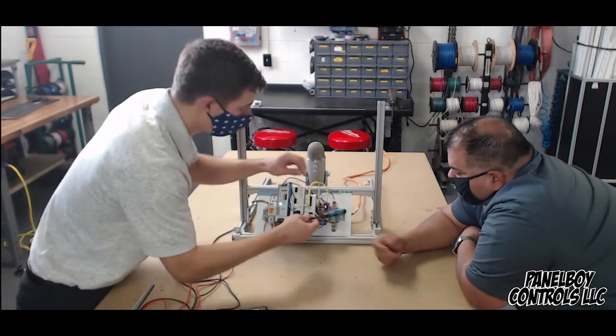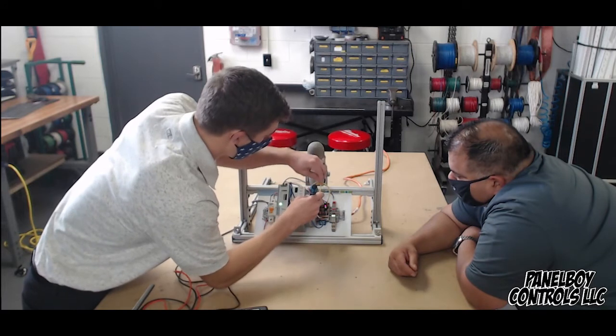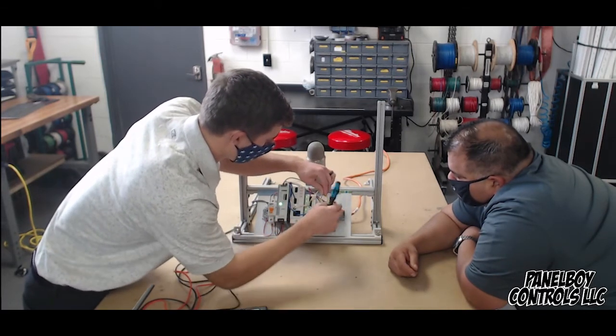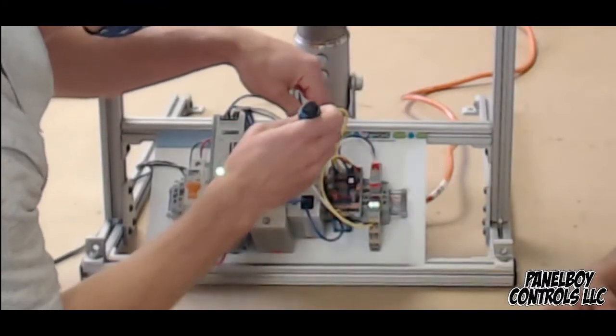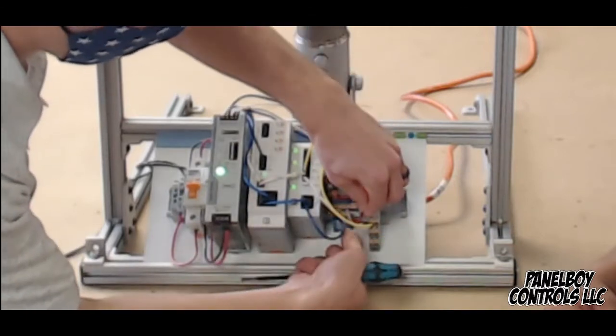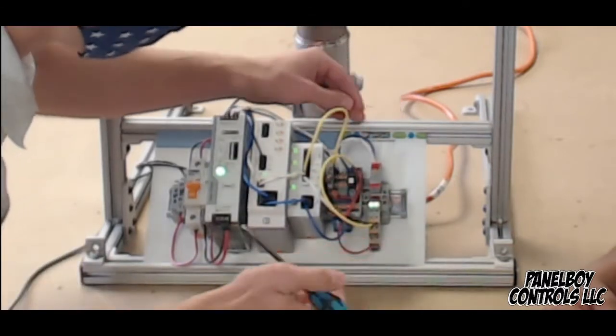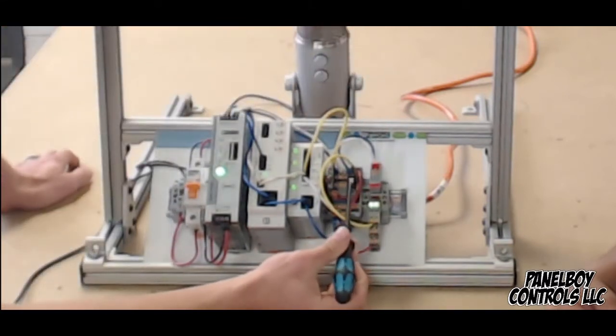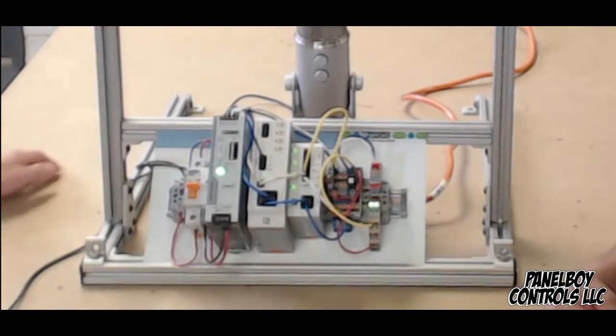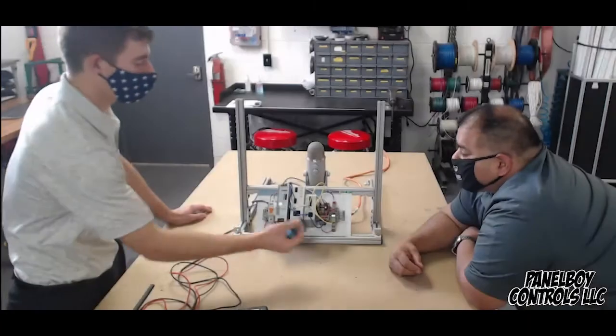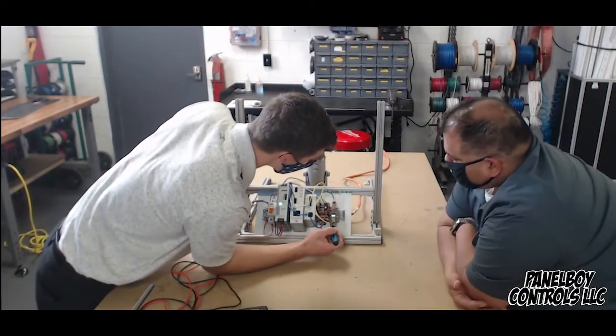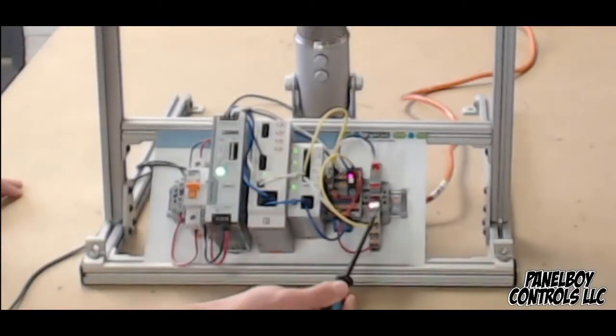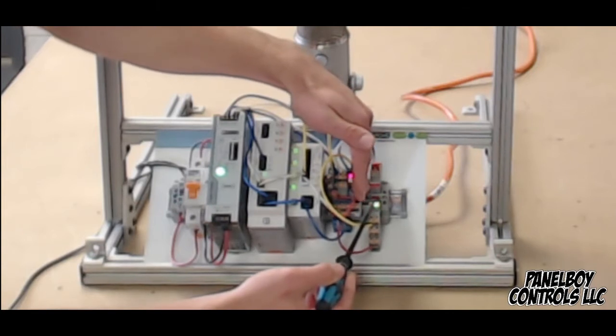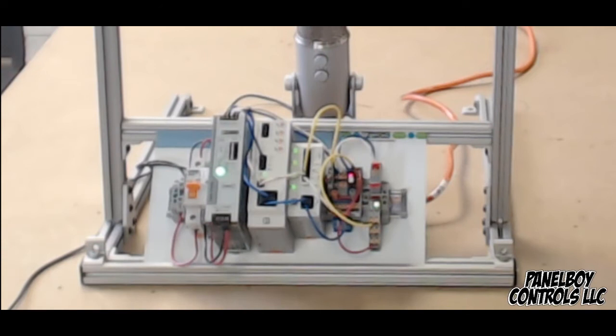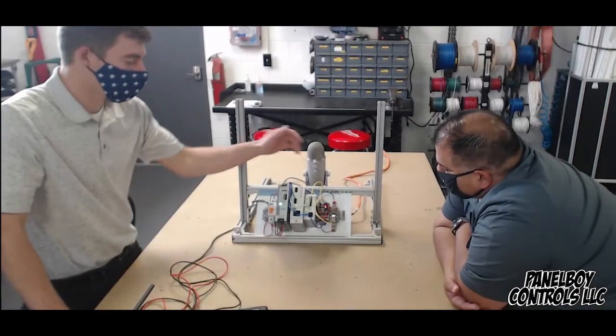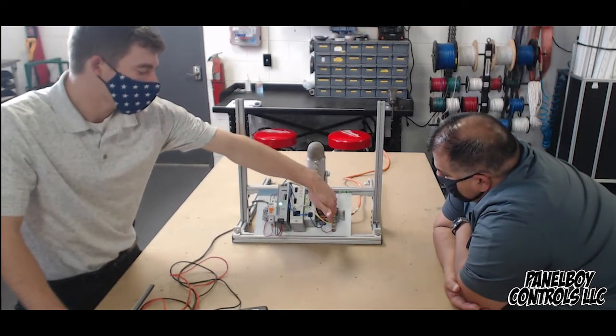So if I can see that screwdriver real quick, I'm going to rewire this. To number 4. I'm also going to move the load wire to this. So if I trip this, you're going to see this light indication turn on. Really what this is doing is giving you, the user, a little more information on what's going on remotely. So I trip this, you see this light, so that went out. This would be in your control panel, so I've got local information. But out in the field, this would typically be run to a PLC, which you can then display information on an HMI. So I've got remote information via this status light.